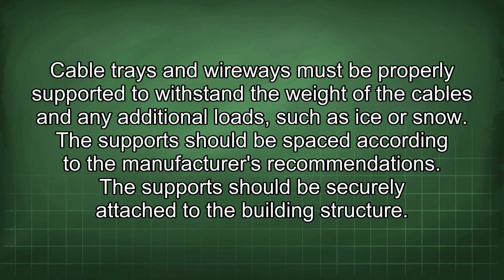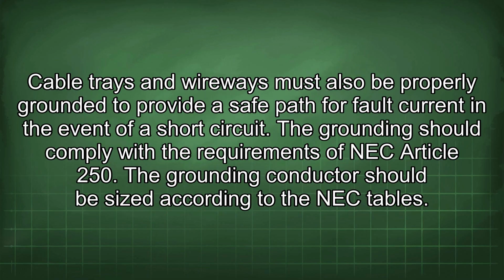Cable trays and wireways must be properly supported to withstand the weight of the cables and any additional loads, such as ice or snow. The support should be spaced according to the manufacturer's recommendations. The support should be securely attached to the building structure. Cable trays and wireways must also be properly grounded to provide a safe path for fault current in the event of a short circuit. The grounding should comply with the requirements of NEC Article 250. The grounding conductor should be sized according to the NEC tables.